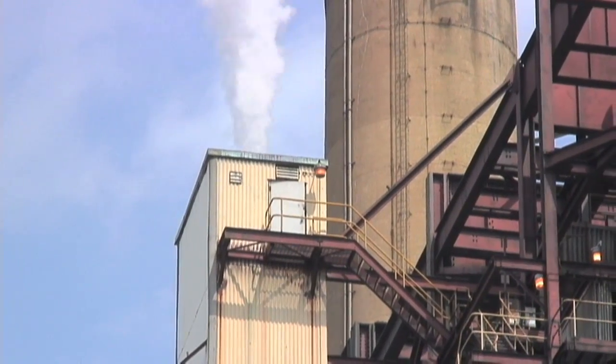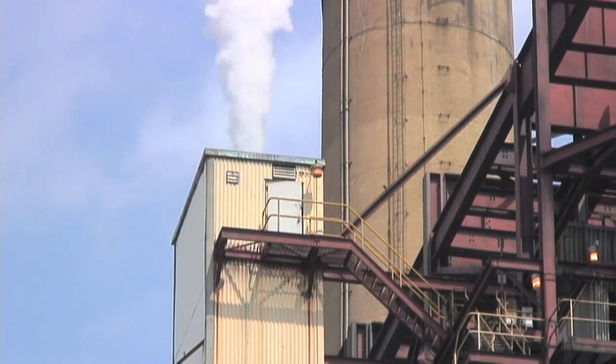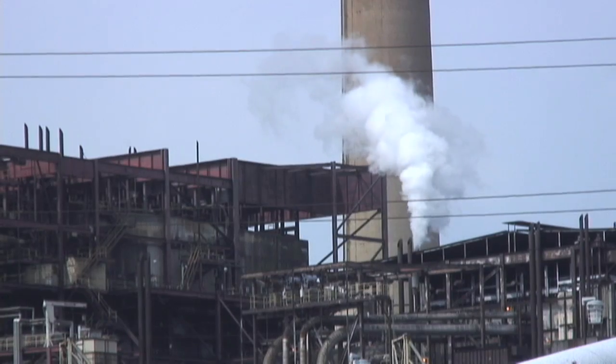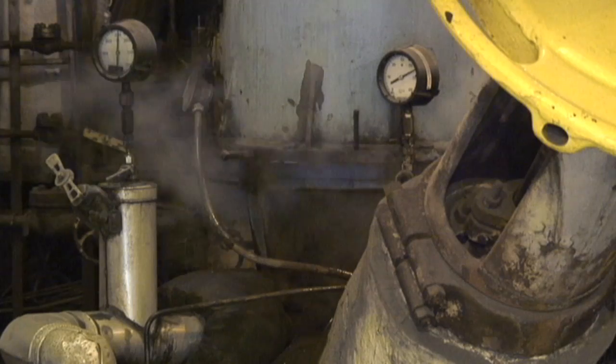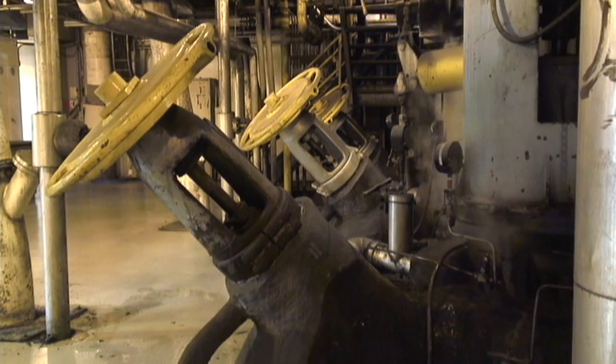At our Chesterfield Power Station, as we have at most of our power stations, we have devices within the furnace that help reduce our nitrous oxide production. Nitrous oxide is a component that can ultimately become smog in the atmosphere, so we like to reduce that right at the furnace. We use low nitrous oxide burners and overfire air to reduce it in the boiler itself.